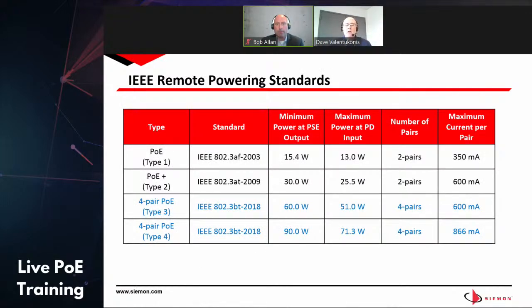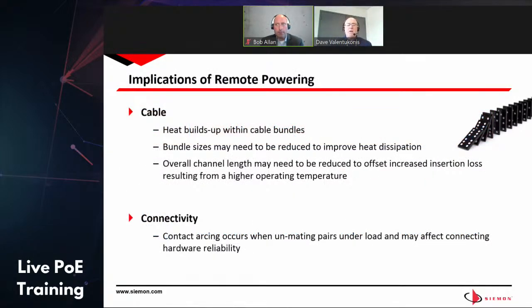When you deliver power, obviously you're adding heat, and there's a manageable number of implications that we'll want to talk about today to make sure that you're properly prepared for it, and then figure out some ideas on how you can address that during the installation of this low voltage cabling. So the primary things we're going to deal with is obviously the heat buildup within the cabling as you add power to the communications.